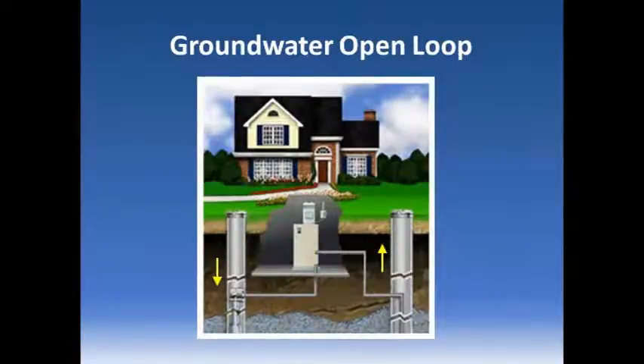The other kind of system is often called an open loop system. There is no actual loop involved, but the term is so common I'm not going to fight it. It means you use groundwater instead of a closed loop heat transfer fluid. This is a so-called doublet system: water is pumped out of one well through the heat pump and then injected into another well. Flow can be reversed when switching from heating to cooling.